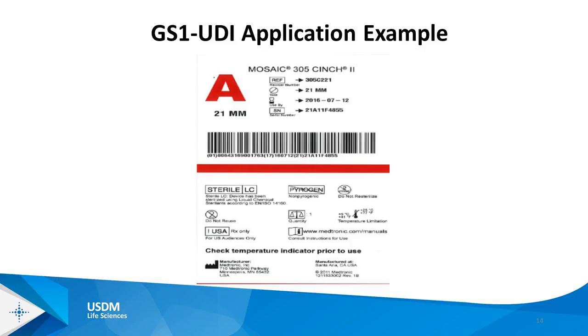So that's UDI on the label. We also see, by the expiration date symbol, the little hourglass, 2016-07-12, which is the standardized date format. So again, all device labels, regardless of their UDI status, need to have dates represented, expiration date and manufacturing date being the two that we talk about primarily, in the standardized date format, which again is a 4-digit year, dash, 2-digit month, dash, 2-digit day, and the day must always be there. And we'll touch a little bit more on that later on.